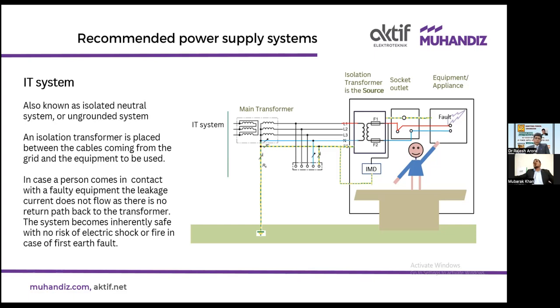So, in an ungrounded system, in case of an earth fault, there is no chance of leakage current. That is why nobody will get a shock. There will not be leakage or anything. The system will continue to run without any problem. The only thing is that the resistance of this phase conductor with respect to ground will reduce because of the earth fault, and it needs to be detected in time so that we can take action. The system is not tripping, right? So if the system is not tripping, there should be a way.